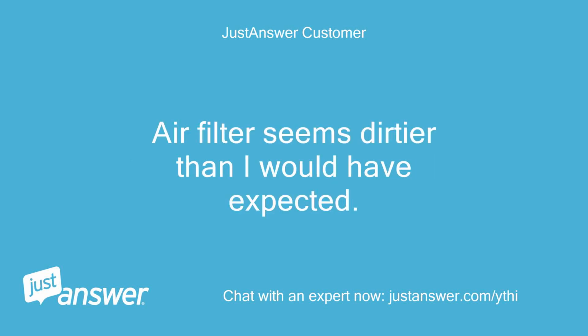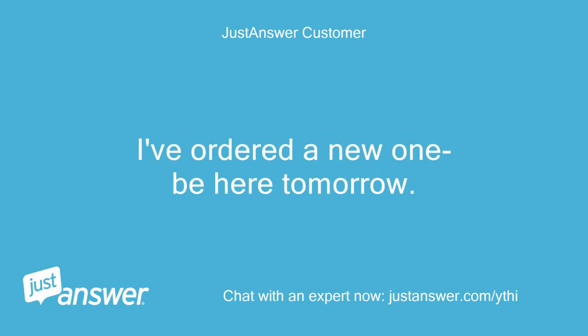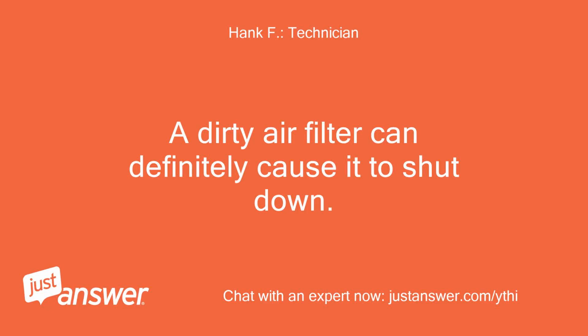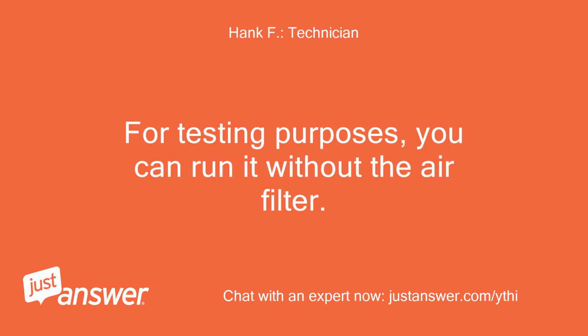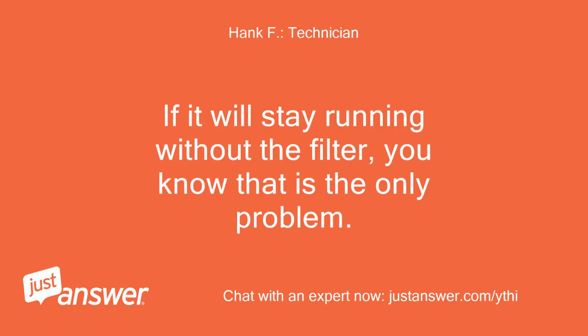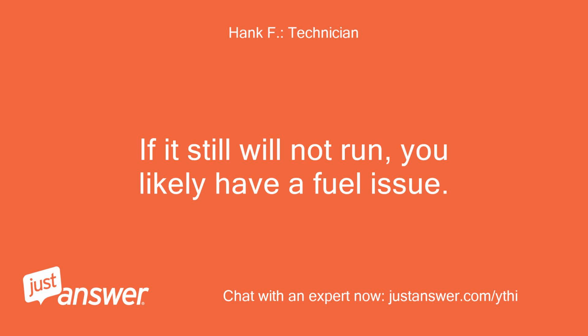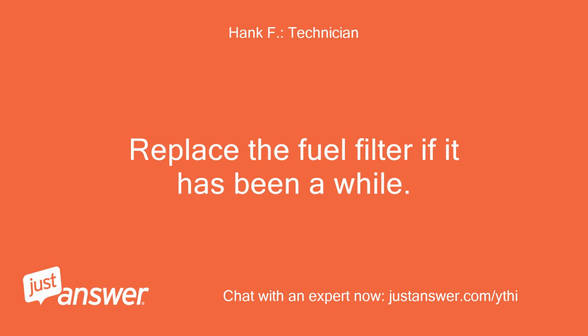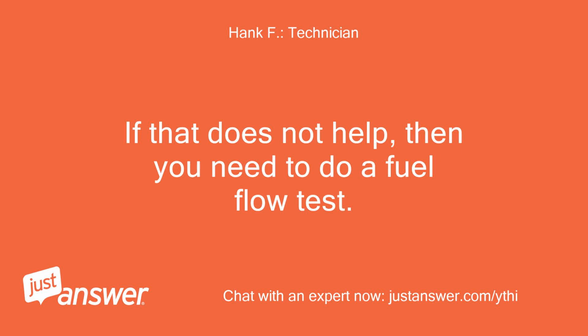Air filter seems dirtier than I would have expected. I've ordered a new one, be here tomorrow. A dirty air filter can definitely cause it to shut down. For testing purposes, you can run it without the air filter. If it will stay running without the filter, you know that is the only problem. If it still will not run, you likely have a fuel issue. Replace the fuel filter if it has been a while. If that does not help, then you need to do a fuel flow test.